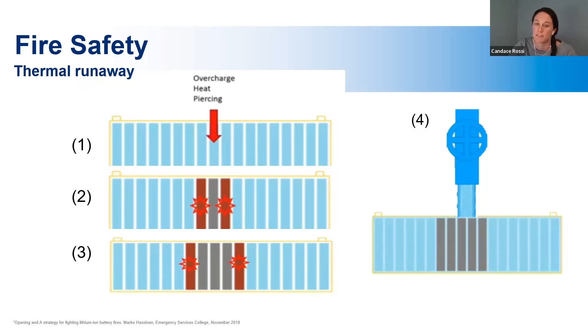So continuing off this diagram, you can see there are a number of components built into the system that can prevent, contain, and mitigate thermal runaway before it occurs or once it's already occurring. These are the different protection methods. In the beginning stage, if there's slight battery abuse, the battery management system can prevent it from spreading. Maybe the cell quality is strong enough and the damage wasn't bad enough that it can prevent it as well. As this continues through the circle, there's also off-gassing detection. You will have gas detectors near the system, and it'll recognize if that's occurring and be able to shut the system off or something along those lines.